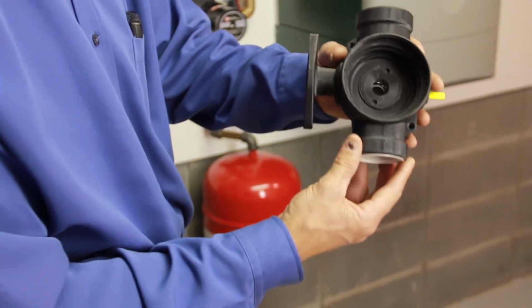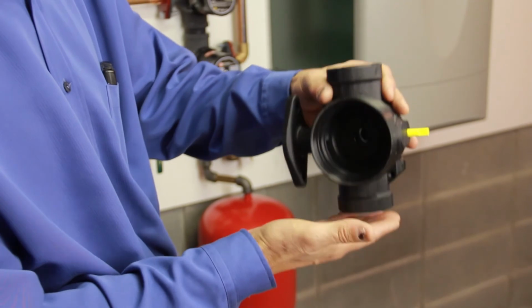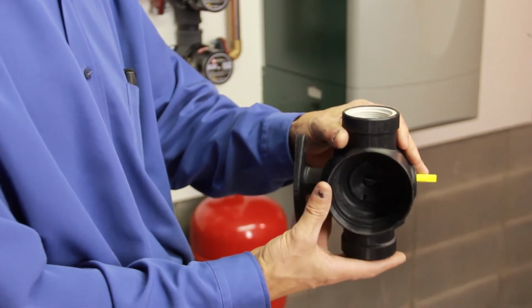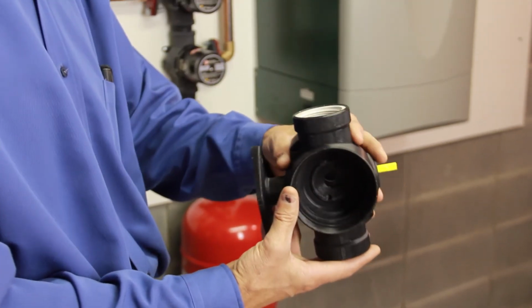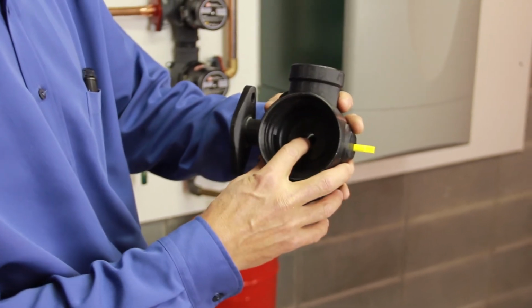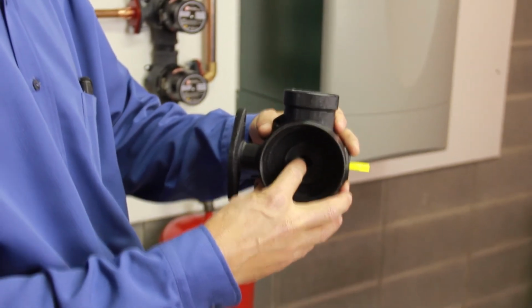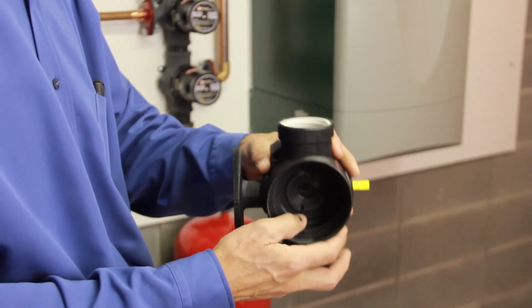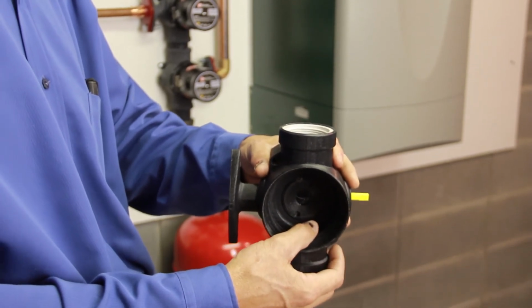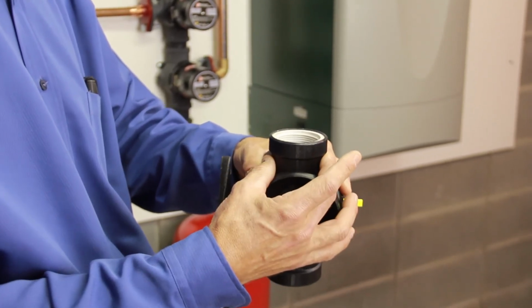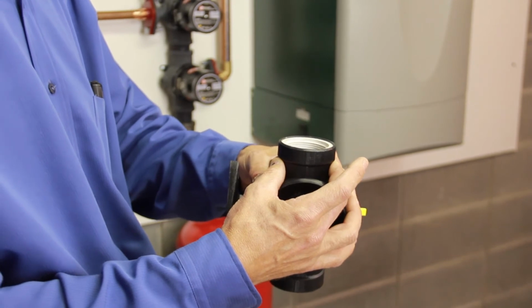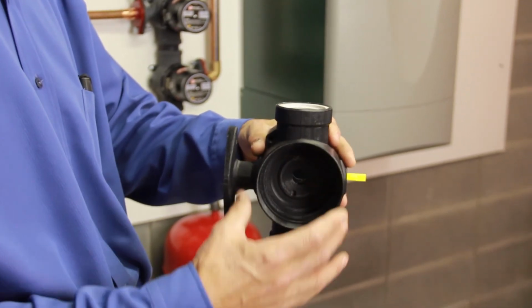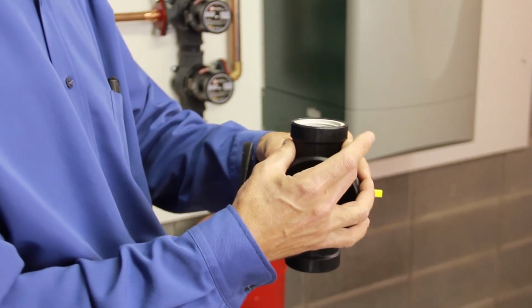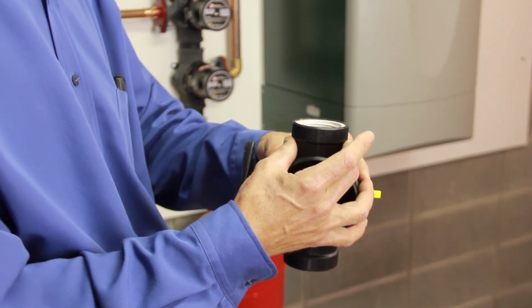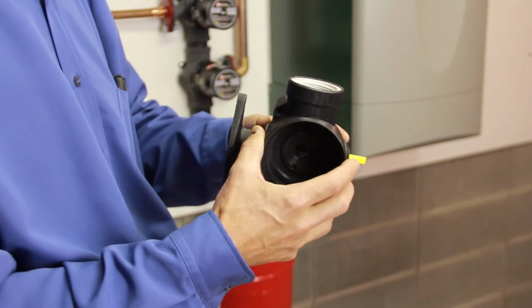As you can see, air that enters the common pipe has a very free path upward. And for the air to get to the impeller, it has to pass through the ball. The likelihood of the air getting to the ball rather than the other passageways around the ball is fairly low. Air that comes through the common body easily passes the impeller and heads up the column toward the air vent.